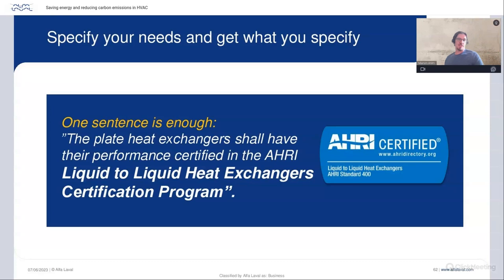And how do you do that? It's very simple in a project. It's one sentence to write into the specs. You only say that the heat exchangers for our project shall have their performance certified in the AHRI liquid-to-liquid heat exchanger certification program or the liquid-to-liquid brazed and fusion bonded certification program, depending on whether it's a gasketed or a plate brazed and fusion bonded heat exchanger. This sentence is what I would recommend anybody write into the spec for a project all the time, given that water, seawater, or glycol is used as the operating media. So it doesn't work with oil or two-phase. It's only single-phase: water-to-water, glycol and seawater.